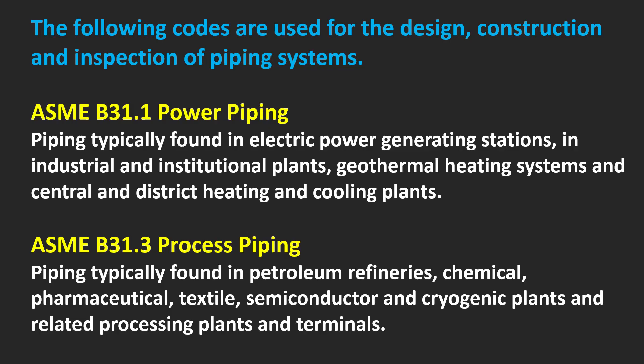The following codes are used for the design, construction, and inspection of piping systems. ASME B31.1 covers power piping — piping typically found in electric power generating stations, industrial and institutional plants, geothermal heating systems, and central and district heating and cooling plants. ASME B31.3 covers process piping — piping typically found in petroleum refineries, chemical, pharmaceutical, textile, semiconductor, and cryogenic plants, and related processing plants and terminals.